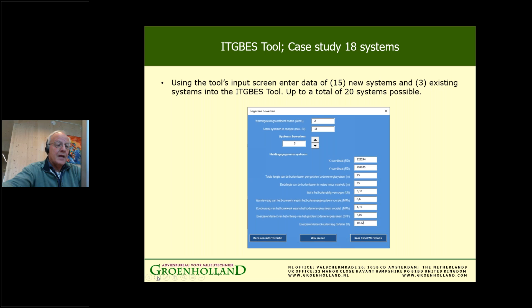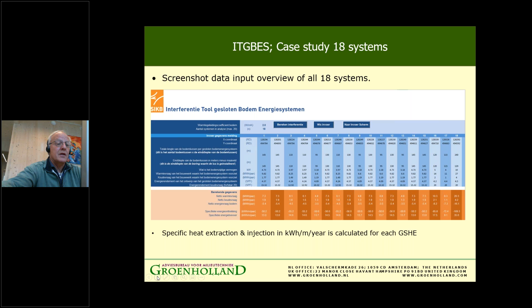And this is what we get. This is an overview in the tool of all the data entered. That is in the blue part that is shown. And then we go to the brown and orange part. They have calculated the specific heat extraction and injection in kilowatt hours per meter per year. So for every location or for borehole, depending on how you filled it in, it is the net extraction rate and the injection rate, both in kilowatt hours per meter per year. So if you have a system that has a net extraction, you have a greater number of kilowatt hours per meter per year in heating than you have in injection.